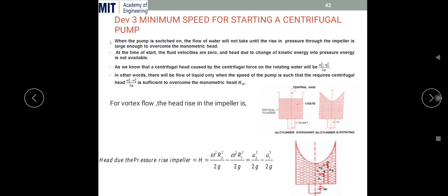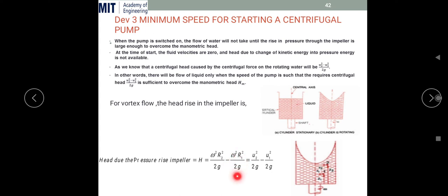This equation is derived from the centrifugal force equation, which is a very basic one. The head rise due to pressure in the impeller H is given as: (ω²r₂²/2g) − (ω²r₁²/2g). It is like final angular momentum minus initial angular momentum, but divided by 2g since we are expressing it as head energy.